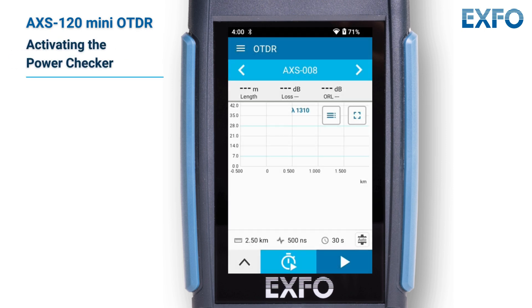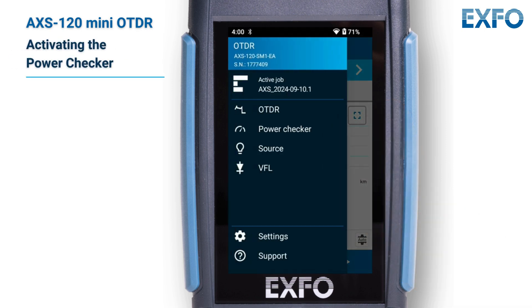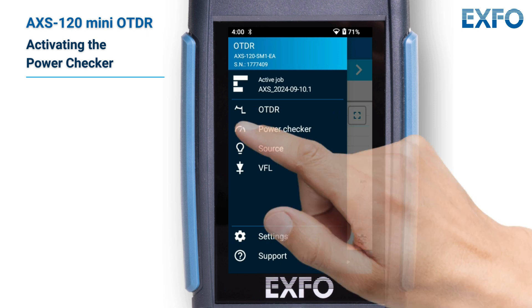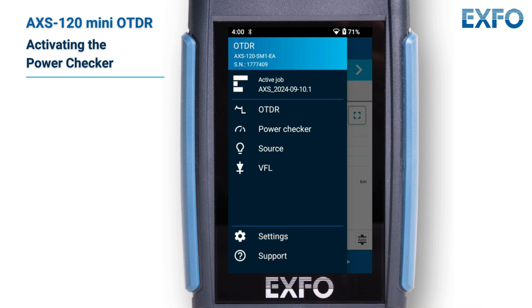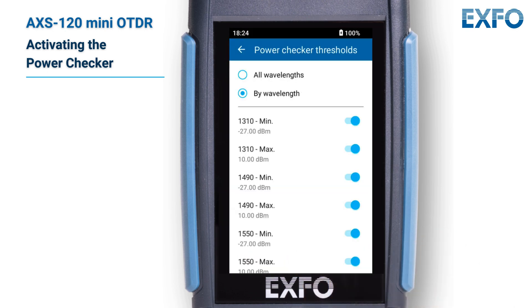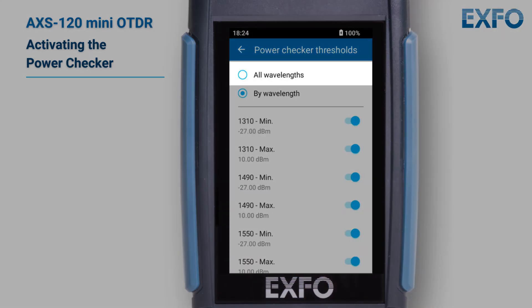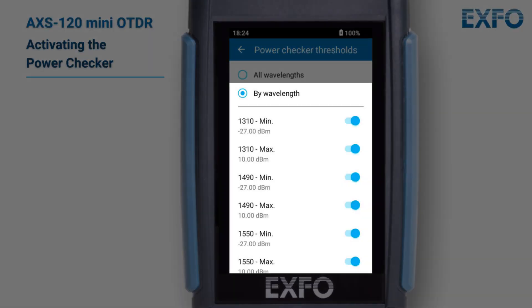To activate the power checker, after connecting your optical source to the input port, select the gauge icon from the main menu. If you haven't yet set thresholds for your measurements, go to settings, then select power checker thresholds, then choose whether they apply to all wavelengths or set specific minimum and maximum thresholds individually.